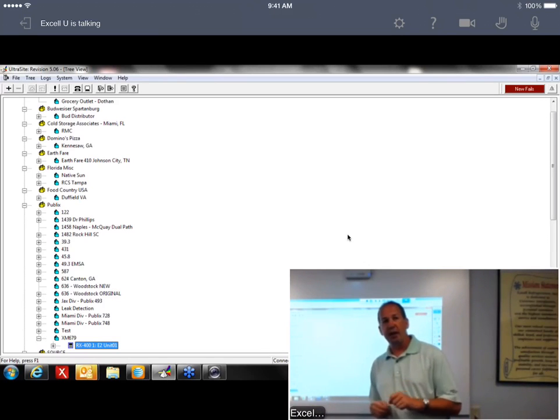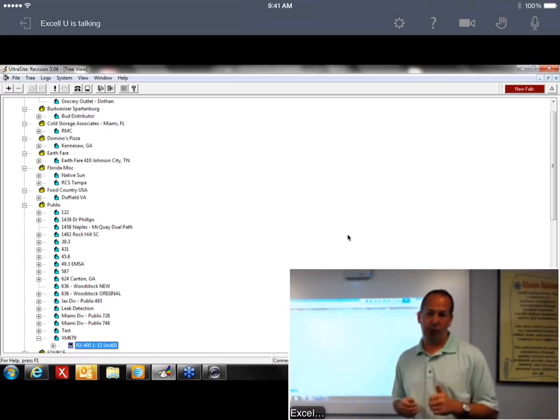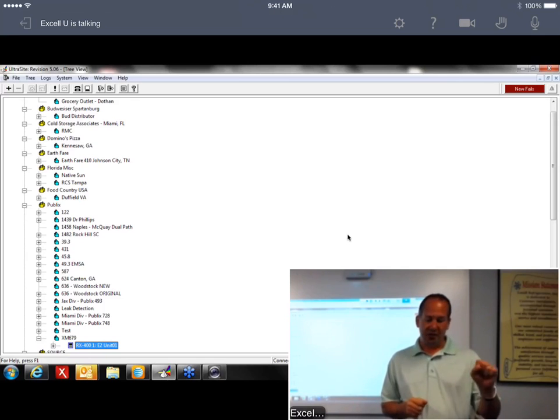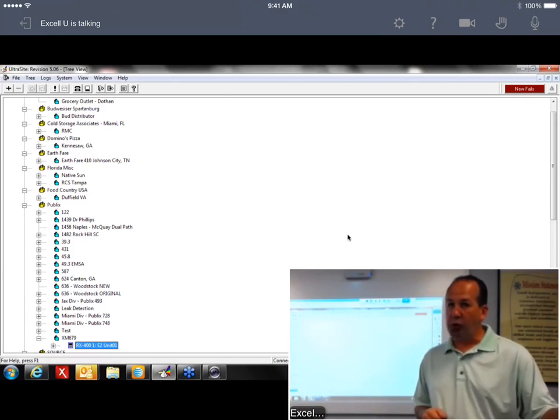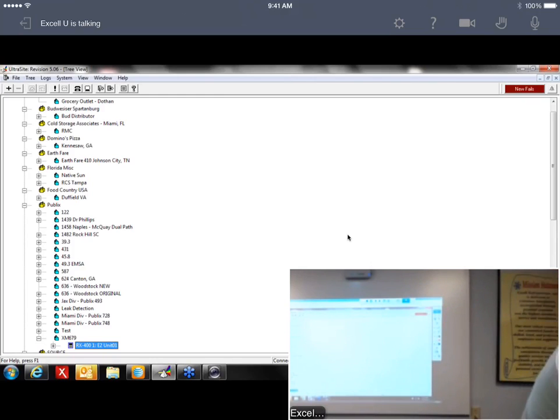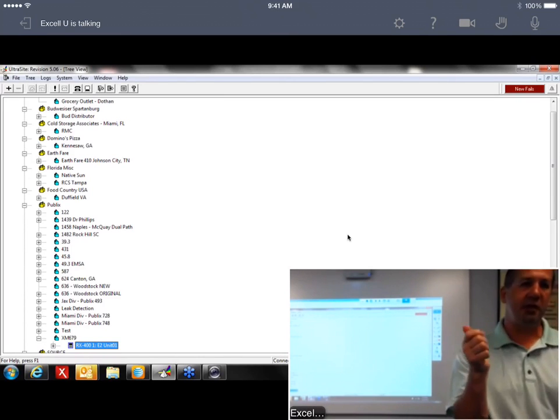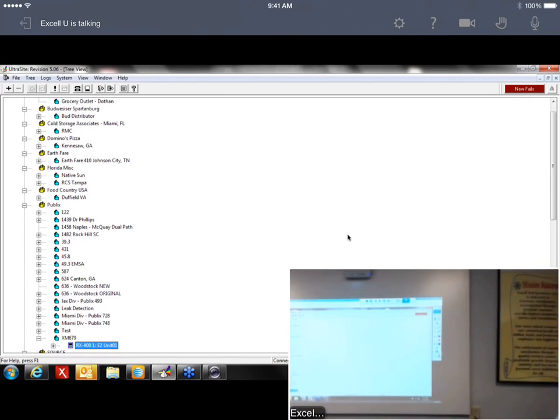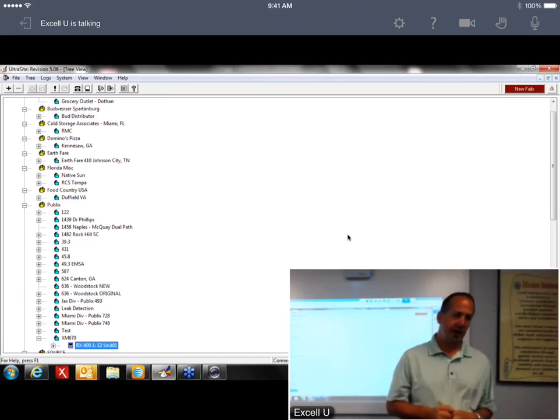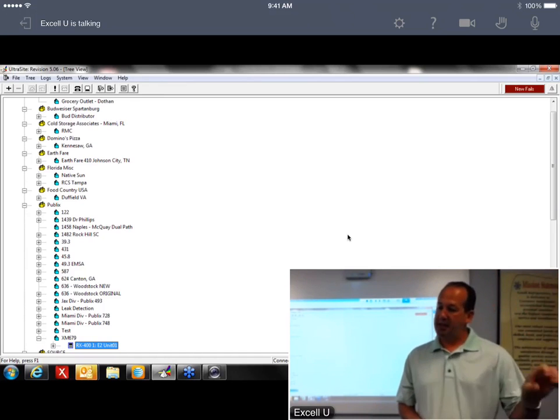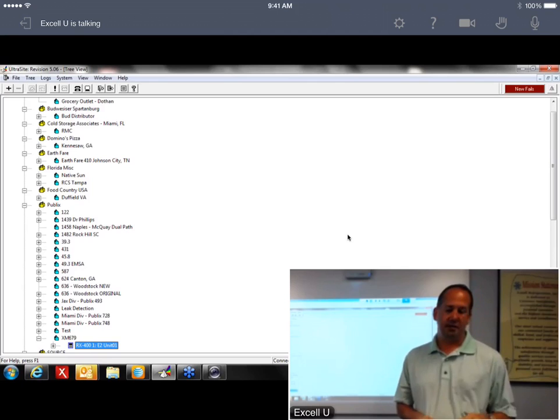Now, if you're doing a retrofit, the old CCBs, I think, were using 24 volt pulse valve solenoid coils. So if you're retrofitting an old CCB with a Dixell, the Dixell will control a 24 volt, but there's a jumper that you've got to set. The jumper is under this box. I'm not going to take it off, but you just pop off the cover of the Dixell, and there's a jumper. It's actually even noted on the front cover, but there's a jumper that you can move so it'll control a 24 volt pulse valve. So if you're doing a retrofit, that's really important to know that jumper's there.